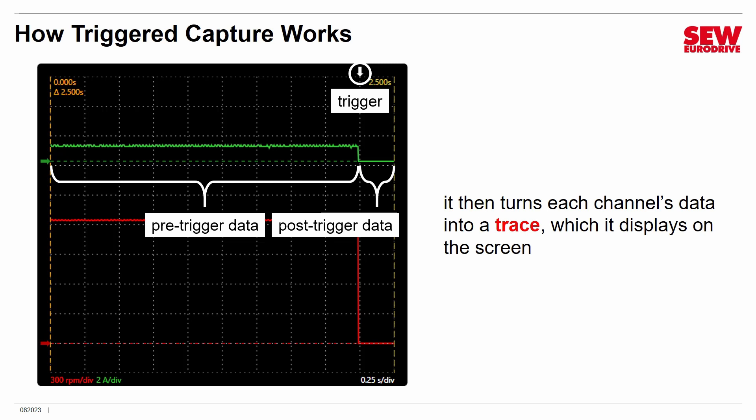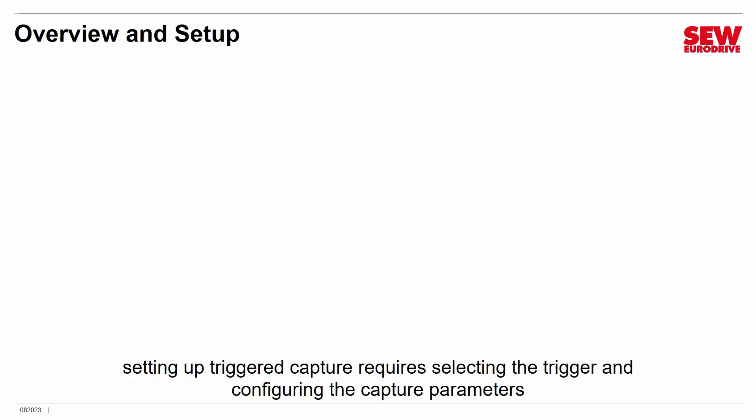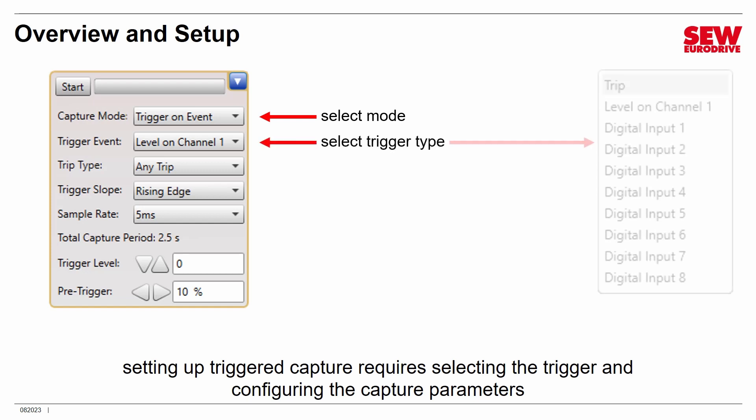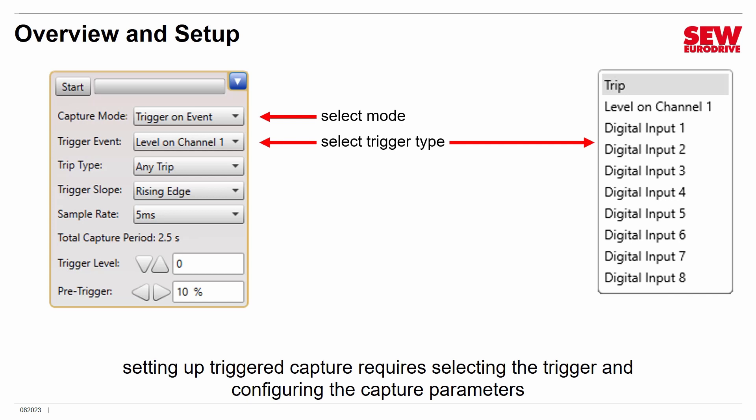Let's talk about how you set up triggered capture — it takes a fair amount of setup. You have to select the trigger and configure the capture parameters, done in the lower right side of the screen. First, pick trigger on event mode — make sure you're not in continuous run mode. Then pick the trigger type; there are several: a trip (that's a fault), a specific level on the parameter being monitored by channel 1, or the digital inputs rising or falling. Note that some options will gray out depending on the trigger type you pick.